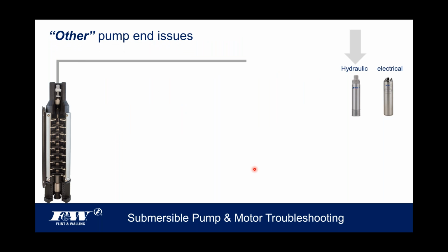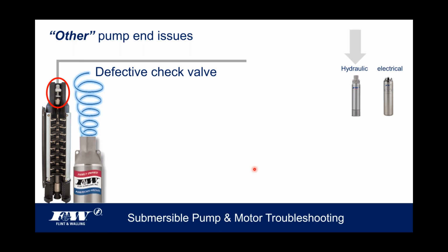Just a handful of other pump end issues here. I want to throw a couple up here. Defective check valves. I'm talking about the ones in the top of the discharge of submersible pumps. I have an opinion on those. I don't like them, never have. I sold pumps back in the 70s. I sold a lot of different brands, submersibles. None of them had check valve issues because none of them had check valves. But somewhere along the way, and I know this is kind of coming across maybe a little weird for a pump guy, but anyway, they put a check valve in the discharge.